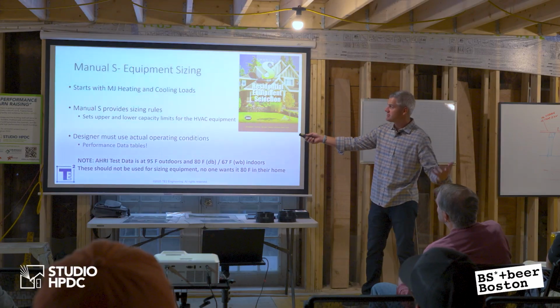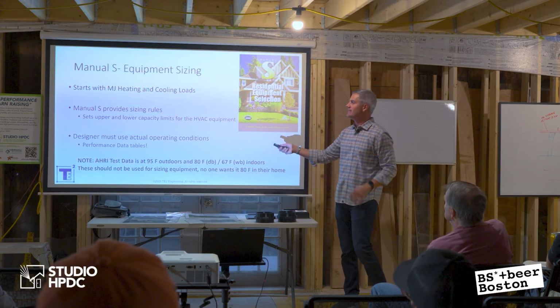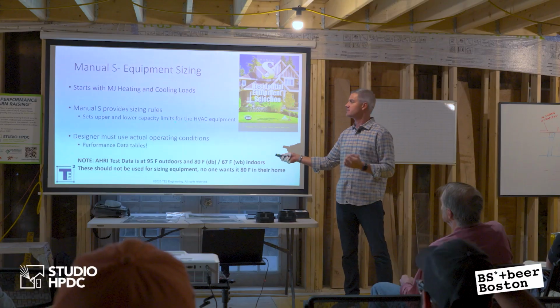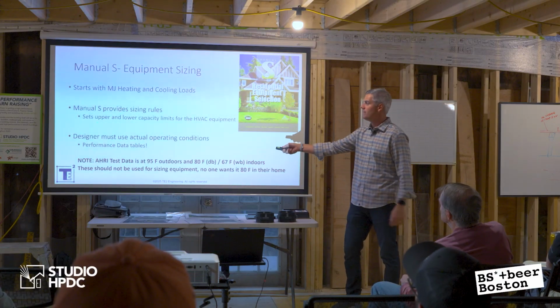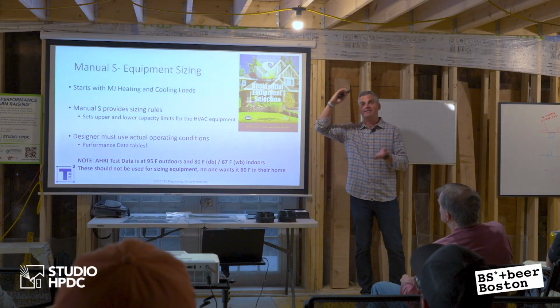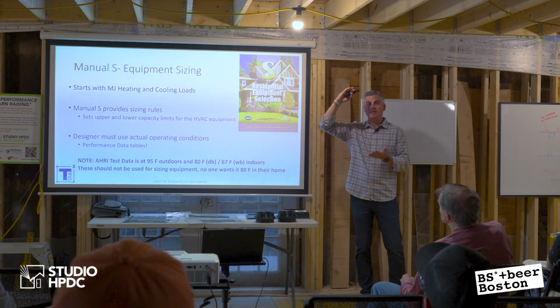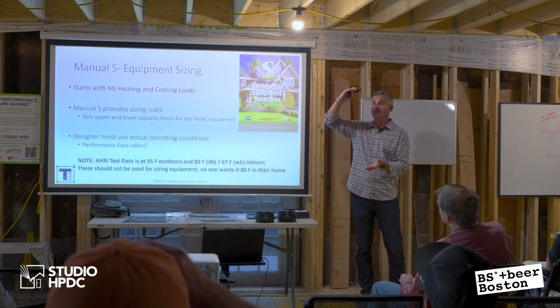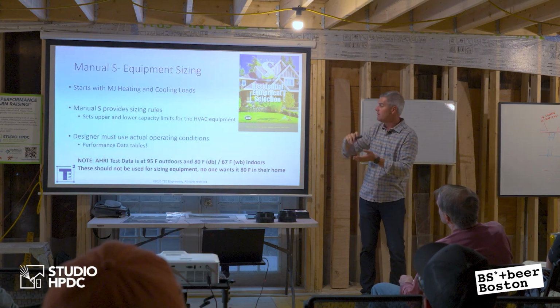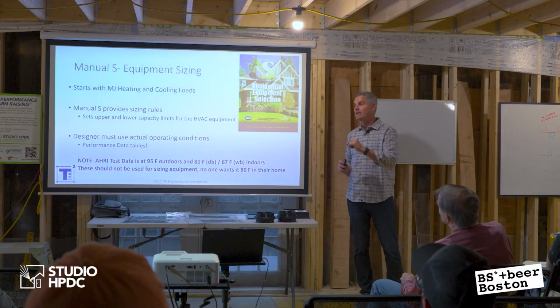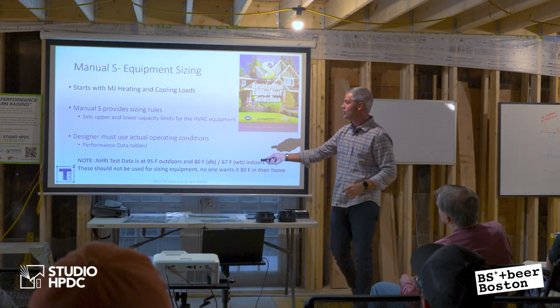Yep. So Manual S is system design. I'm not going to go through all of it, but basically when you have your heating and cooling loads defined, you have to size the heat pump, and it sets an upper and lower capacity on the HVAC system. So it doesn't let you oversize the HVAC, it doesn't let you undersize the HVAC, it puts you in the right spot.